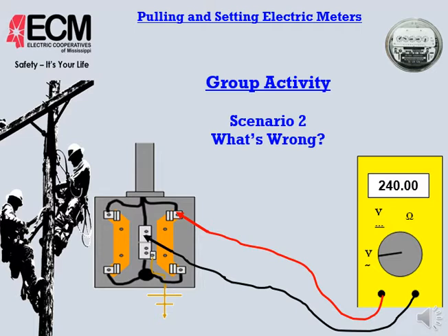And on the other flip side, if the coin had 3 sides, I guess we could look at it from this direction. If the electrician marks the wires wrong coming out of the weatherhead, and we squeeze it up thinking we're squeezing it up right, that could cause the same problem. If we had taken the time to ring that wire out before we made those connections, we definitely could have found that. But before we pick up the phone calling the electrician and saying, "Hey, I think you made a mistake," let's backtrack and check our connections at the transformer and the weatherhead, the things that we have done as a utility, to make sure that we are correct before we start calling electricians.